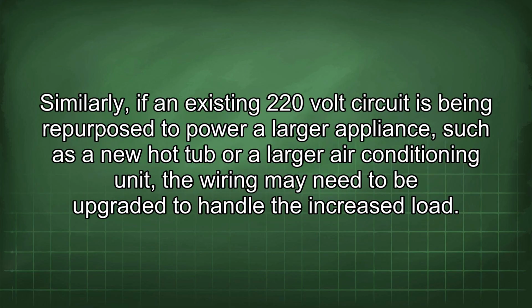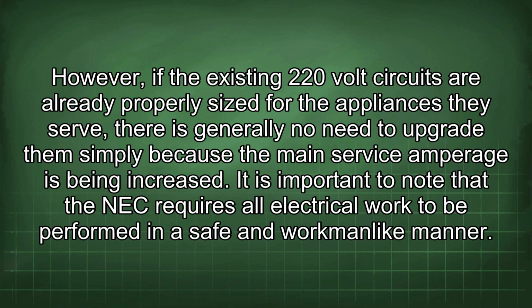Similarly, if an existing 220 volt circuit is being repurposed to power a larger appliance, such as a new hot tub or a larger air conditioning unit, the wiring may need to be upgraded to handle the increased load. However, if the existing 220 volt circuits are already properly sized for the appliances they serve, there is generally no need to upgrade them simply because the main service amperage is being increased.